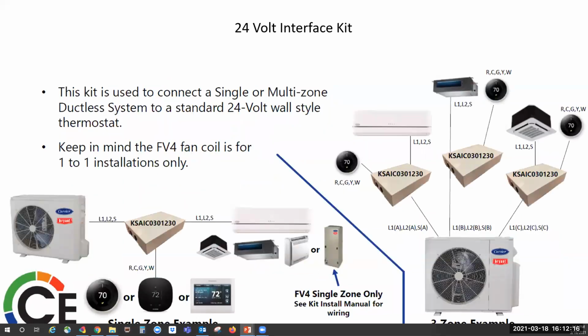24 volt interface. This can be used with most 24 volt thermostats. When using a 24 volt thermostat, you'll need to refer to the installation manual on the interface kit for the settings that you'll need. You do not use a heat pump thermostat. Even if you have a heat pump system, you do not use the heat pump thermostat. You'll use the heat cool only thermostat, and let the algorithms inside that kit decide on what's going to happen and when.